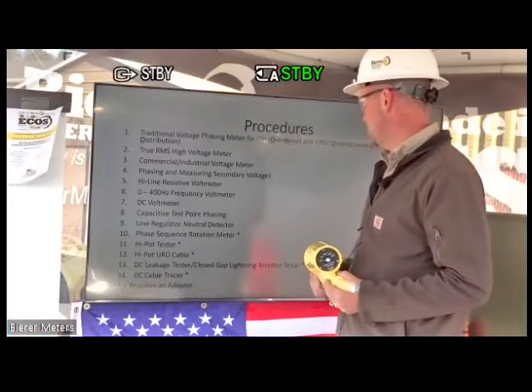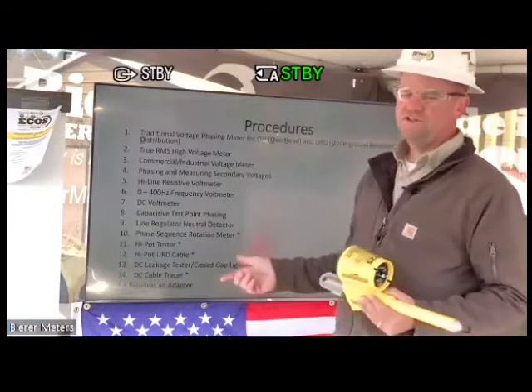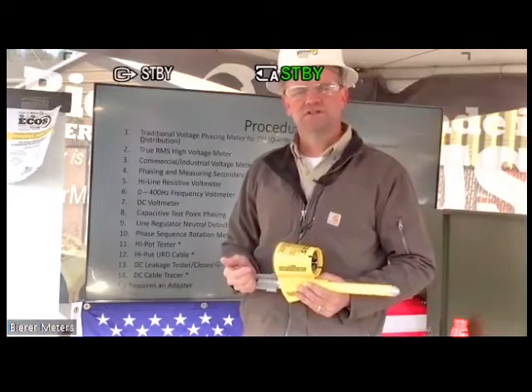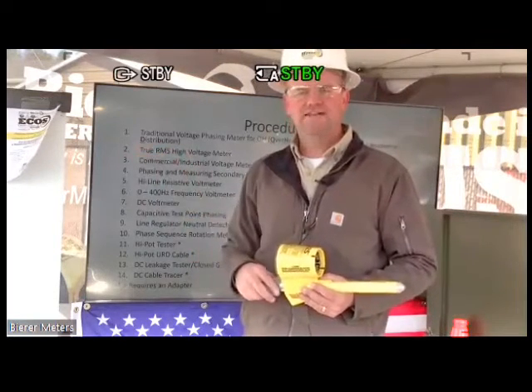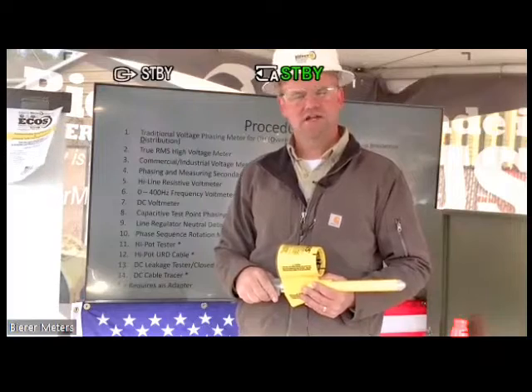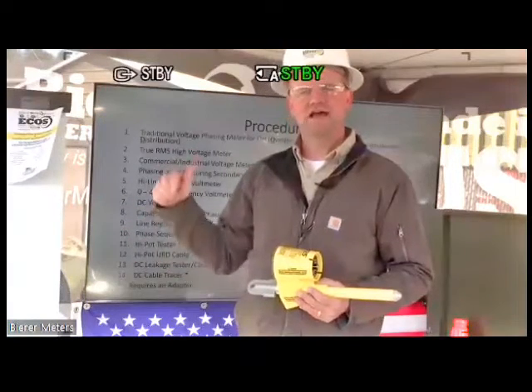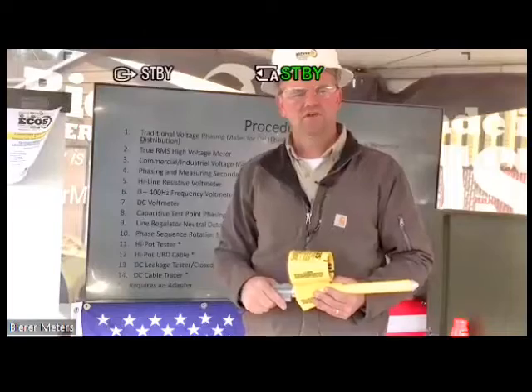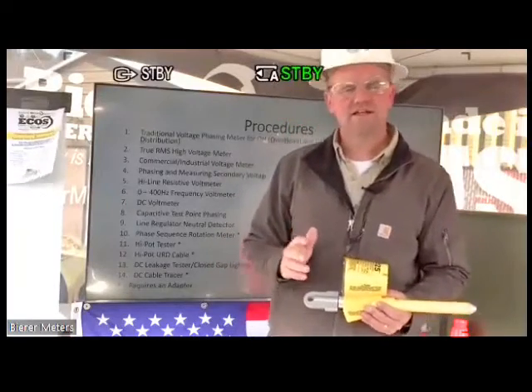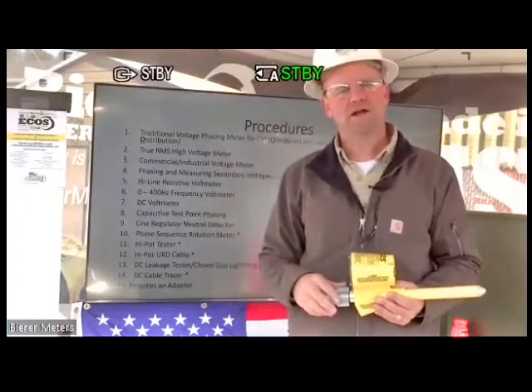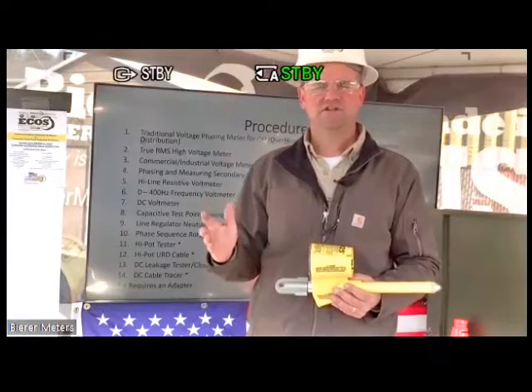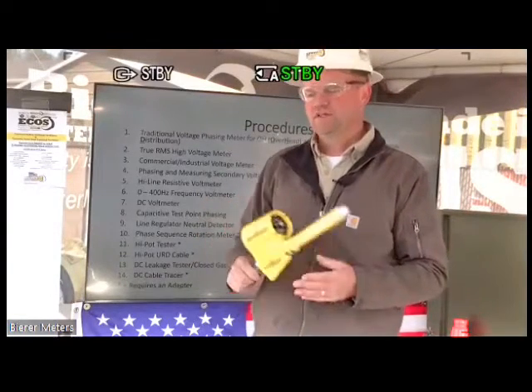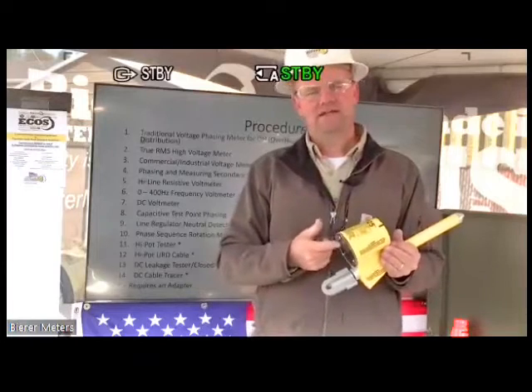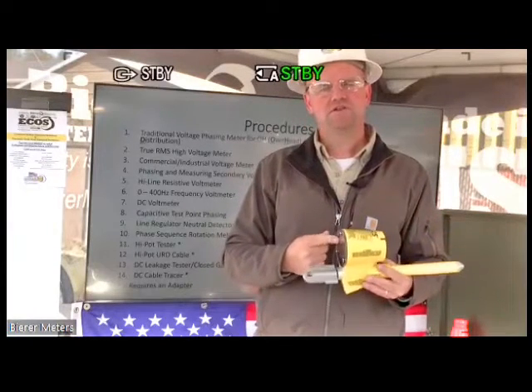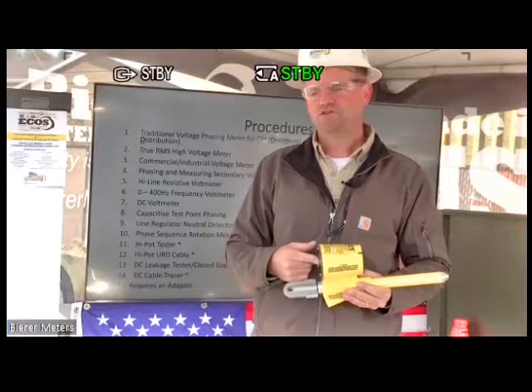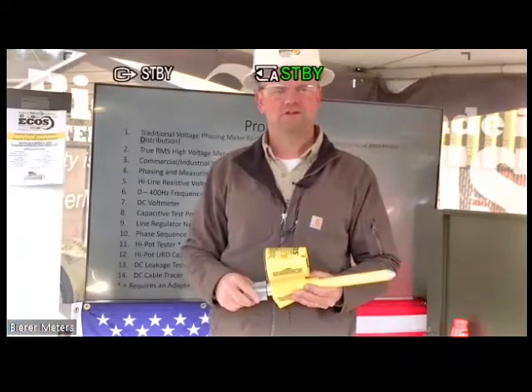A DC leakage tester. As far as testing lightning arresters, you would utilize the high pot adapter again, just like high potting URD cable; you would essentially high pot the arrestor. Normally the industry standard is about 20 microamps. Anything beyond that is considered a failed arrestor. So you can determine that by the display, how much leakage you have on that arrestor versus what's good or bad, basically a pass or fail.